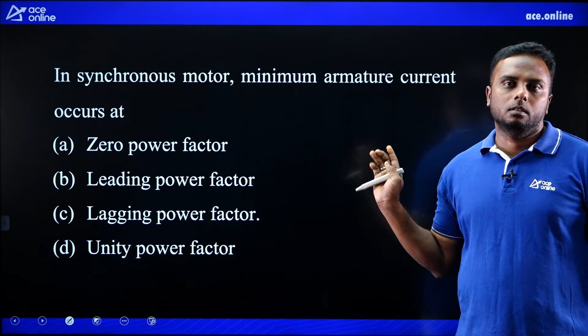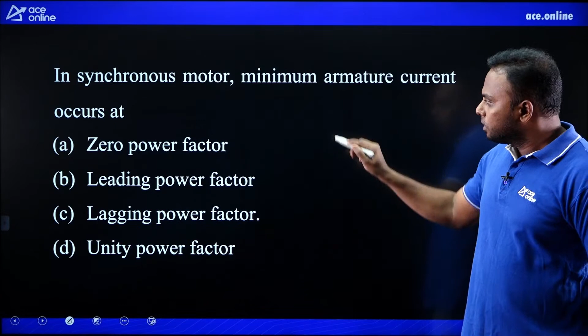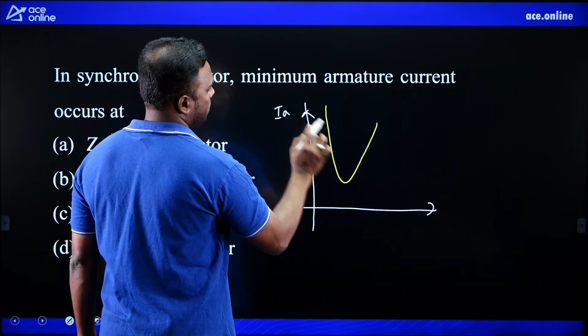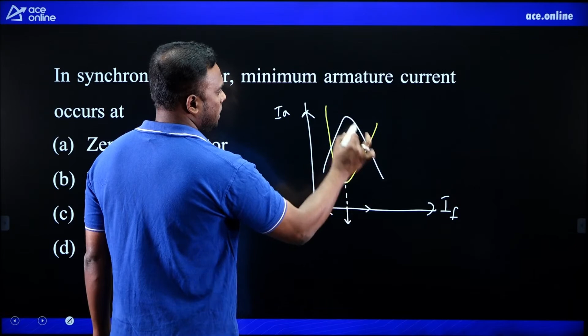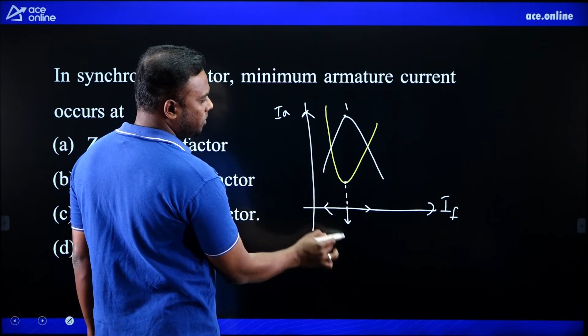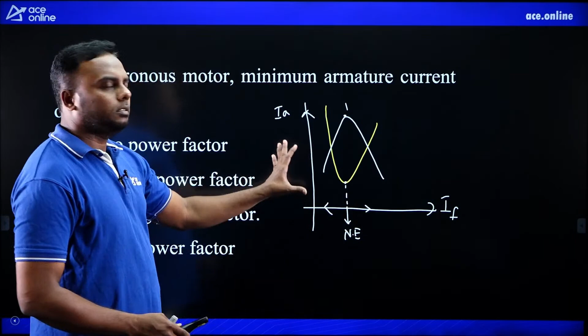If you remember the V curve of synchronous machines, whether alternator or synchronous motor, the V curve is drawn between armature current and field current. This is armature current, this is at unity power factor, and here the armature current is minimum; this is called normal excitation. Wherever we get UPF, the inverted V curve looks like this. Here we get UPF where power factor is maximum, equal to 1. So at unity power factor, armature current will be minimum; this is called normal excitation. So for both alternator and motor, it's the same graph.